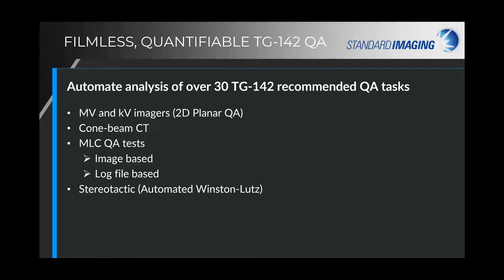We have a stereotactic module with automated Winston-Lutz, which checks the rotational accuracy of the machine. This is available as part of the full package or as a standalone module. We also do radiation light field, star shot analysis for gantry, couch, and collimator — all done with the EPID except for one test requiring film. And we have an IGRT module, which is a warehouse for your daily 2D and 3D matching components, which you can trend across a calendar timeline.